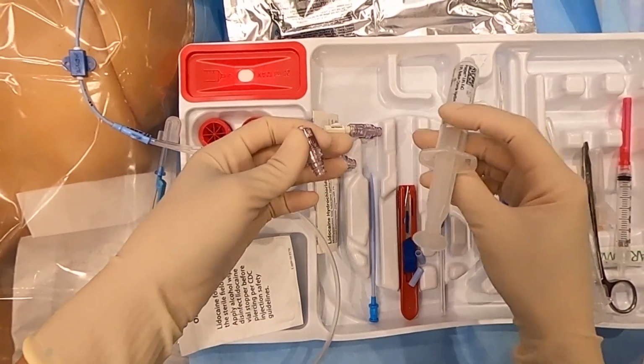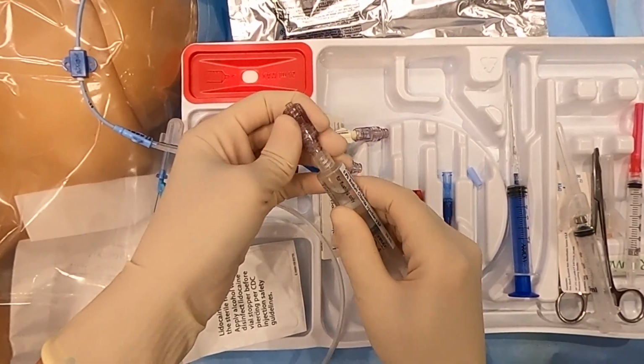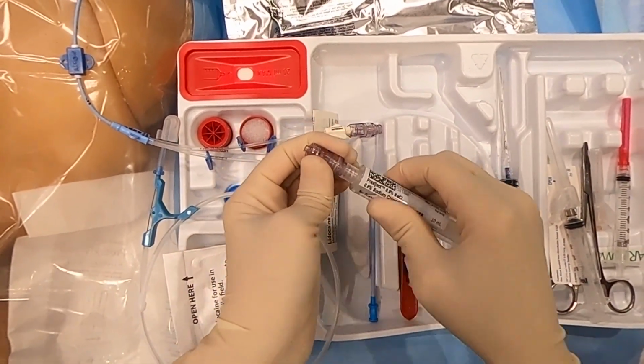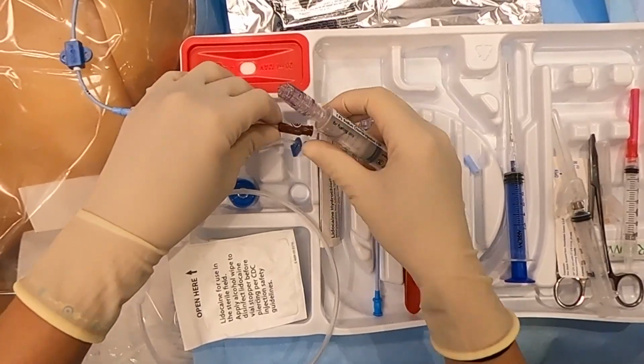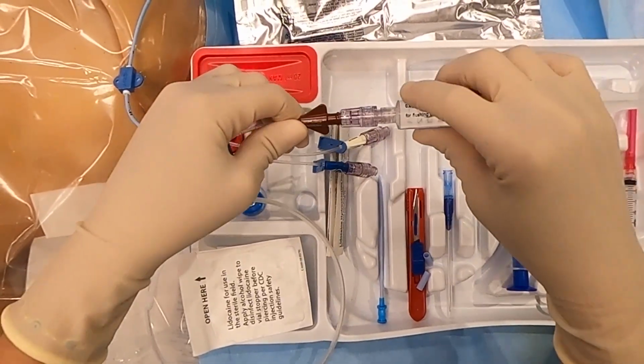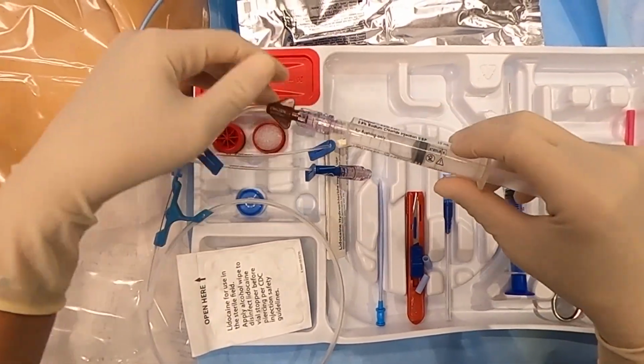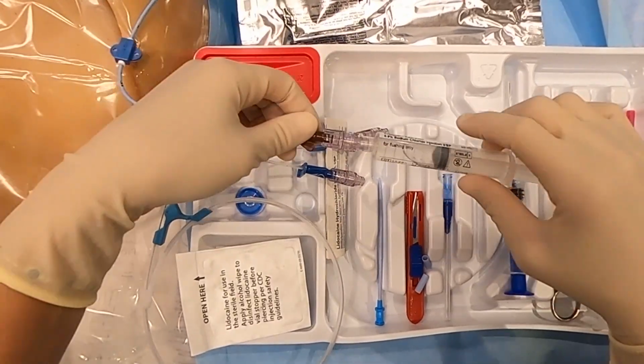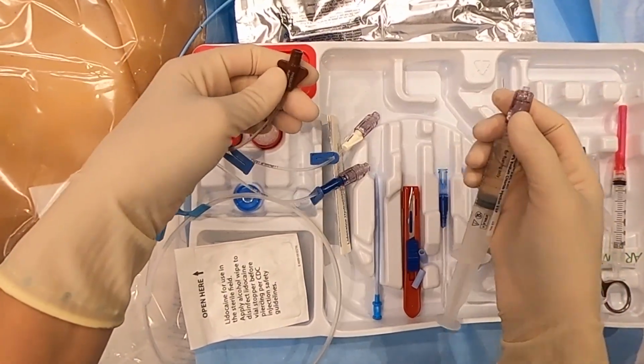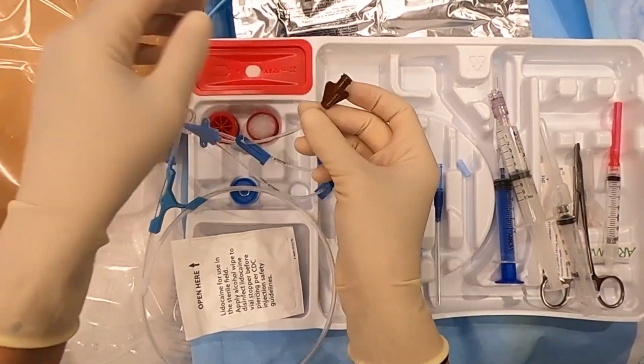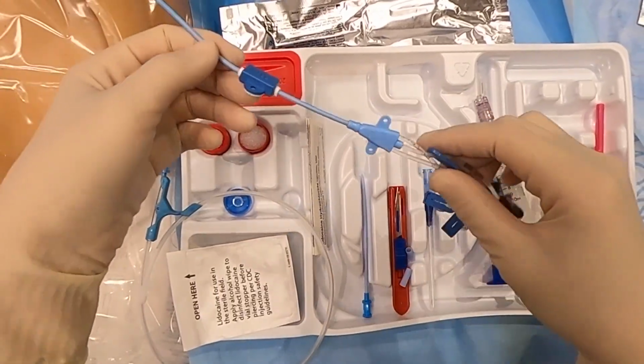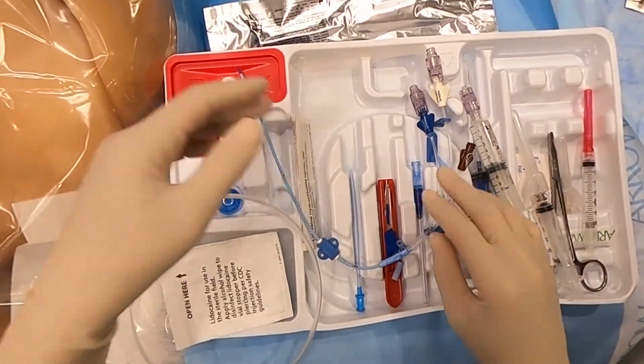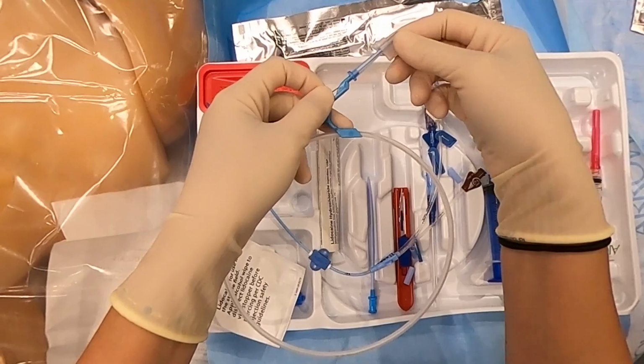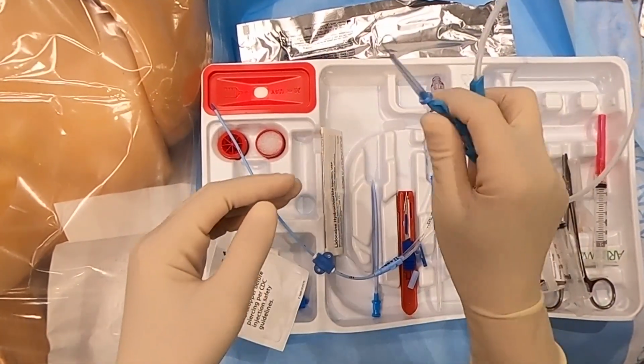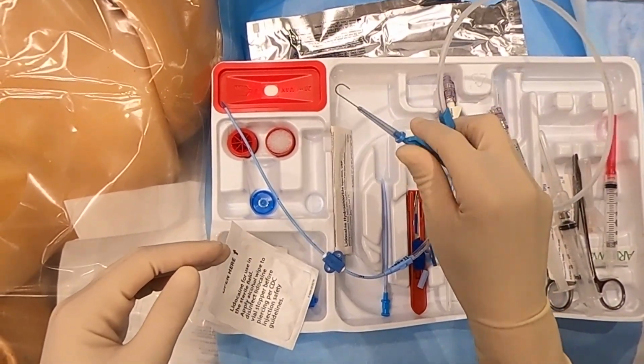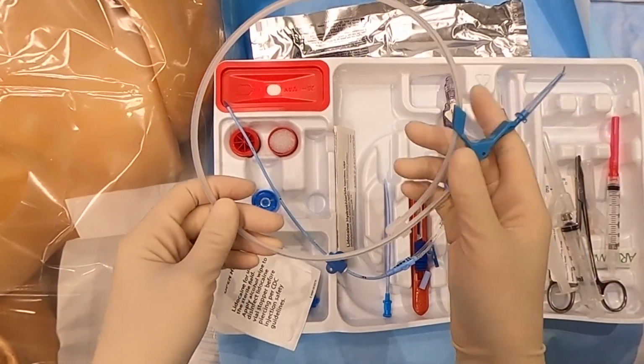To flush the brown port, you can take the third cap and attach it to the flush before you flush the last port. Just remember to keep the brown port without the cap on. Next, check your guide wire. Remove the small cap and make sure the guide wire moves freely within the sheath.